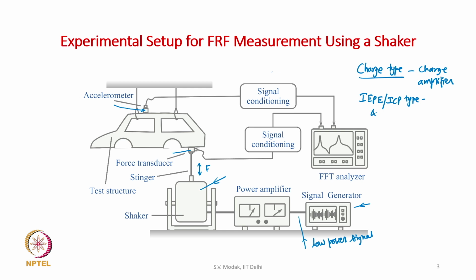So, if the FFT has ICP compatible input ends, then no signal conditioner in between the transducers and the FFT analyzer is required.